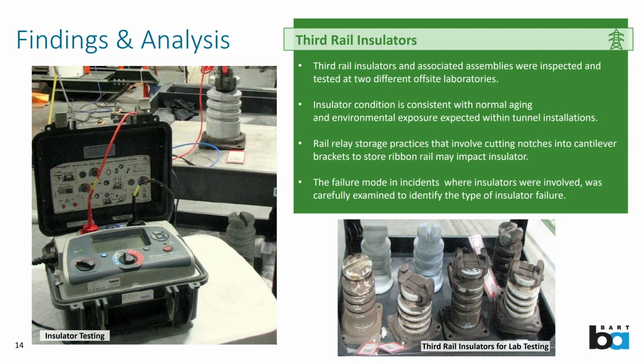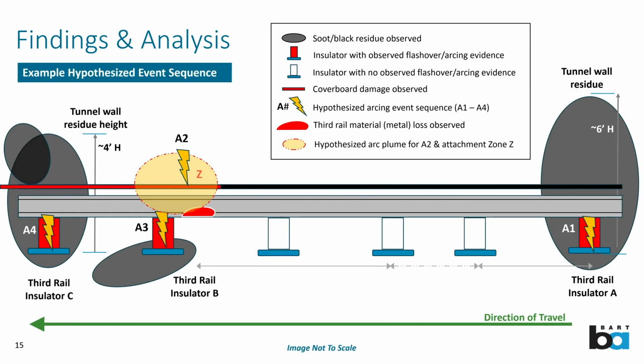Let's go back one slide to point out that the team has extensive experience analyzing insulator failures and determining whether the insulator was the initiating cause. We'll provide an example of that on the next slide, from one of the incidents, showing how we determine if the insulator was the root cause or not.